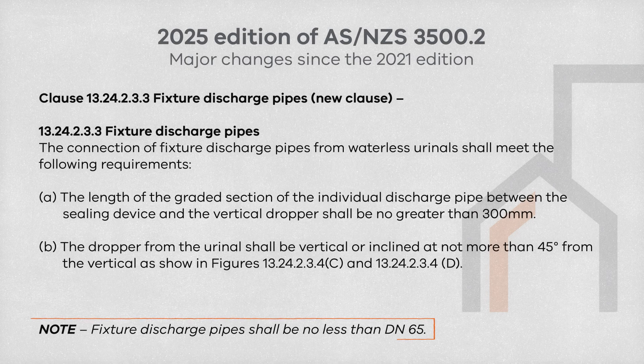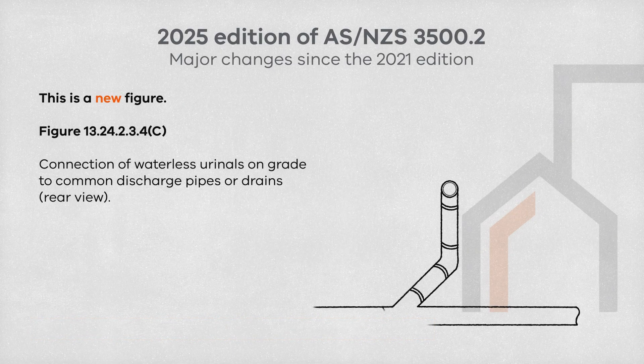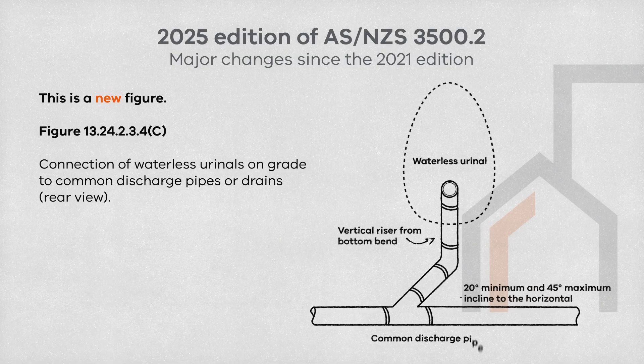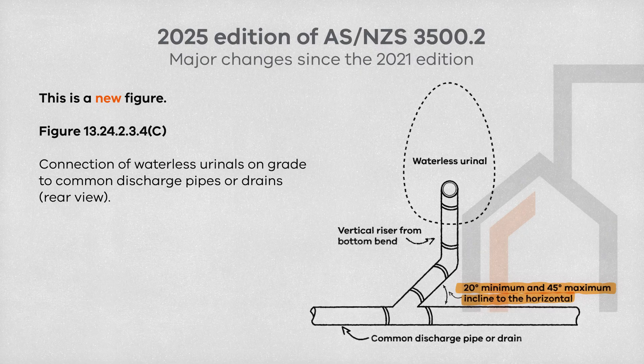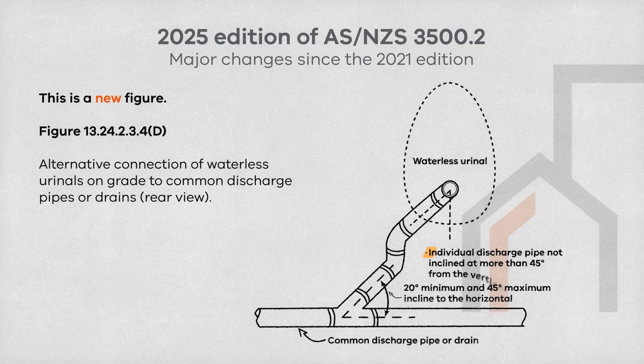This new clause outlines the requirements that fixture discharge pipes from waterless urinals must comply with. A new figure illustrates the connection of waterless urinals on grade to common discharge pipes, showing the 20-degree minimum and 45-degree maximum incline to the horizontal drain. Another new figure shows the individual discharge pipe not inclined at more than 45 degrees from the vertical.